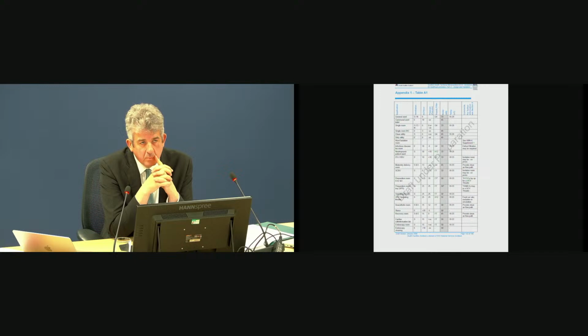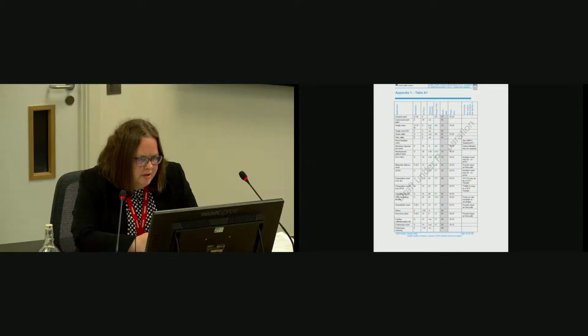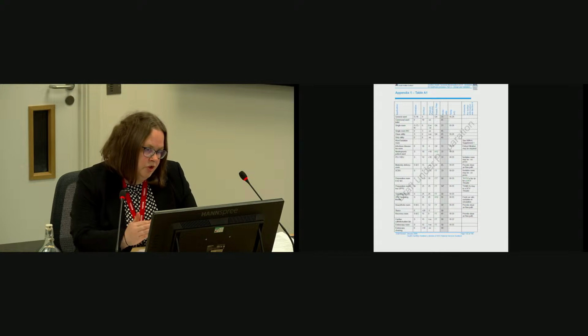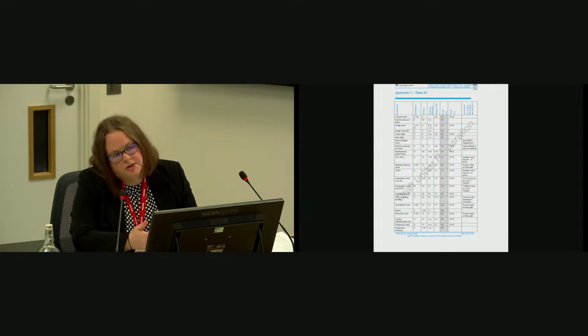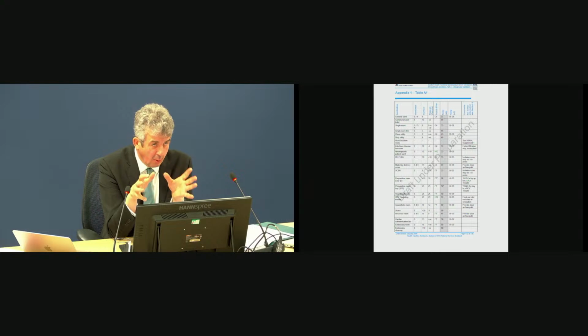Yes, but I would prefer to see a lobby there. Why? Because if you're just focusing on the room and not the corridor, you can have ingress of contaminated air into the room, and your only protection is a door, one door. So if the door is left open for a period of time, the pressure will drop, and you will get ingress of contaminated air. So if you're in a situation where you do not have a HEPA-filtered corridor, adding a lobby, it's going back to that positive pressure cascade that I described, provides that additional layer of protection from unfiltered corridor air.